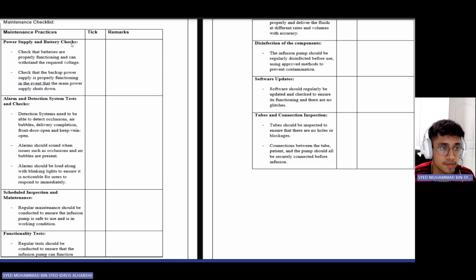For example, in the first box, power supply and battery checks. Users should check that the batteries are properly functioning and can withstand the required voltage. They should also check that the backup power supply is properly functioning in the event that the main power supply shuts down so that the liquid can be infused into the patient despite the first power supply being shut down. Secondly, the alarm and detection system tests and checks. Detection systems need to be able to detect occlusions, air bubbles, delivery completion, front door open, and keep vein open. Alarms should also sound when issues such as occlusions and air bubbles are present. Alarms should be loud along with blinking lights to ensure it is noticeable for users to respond to immediately.